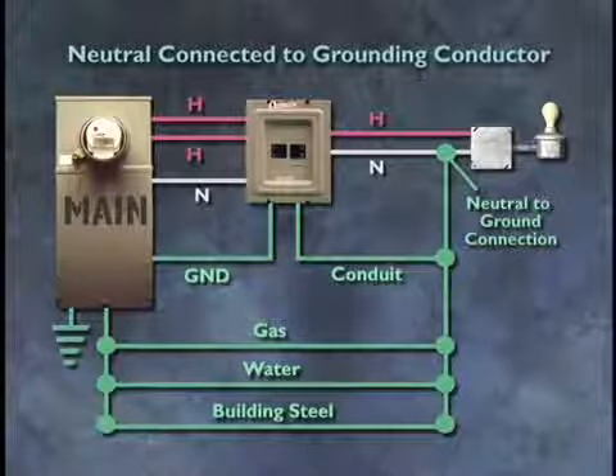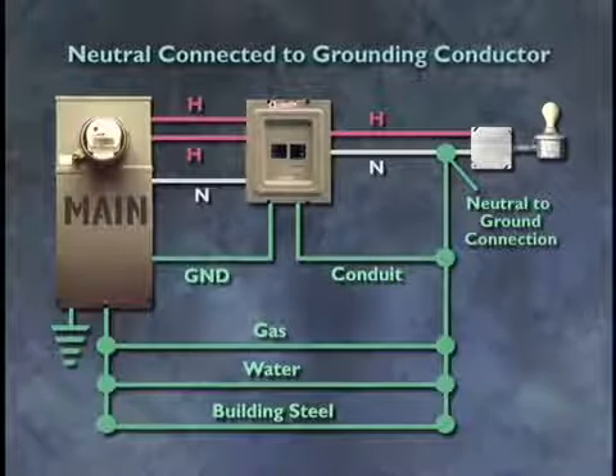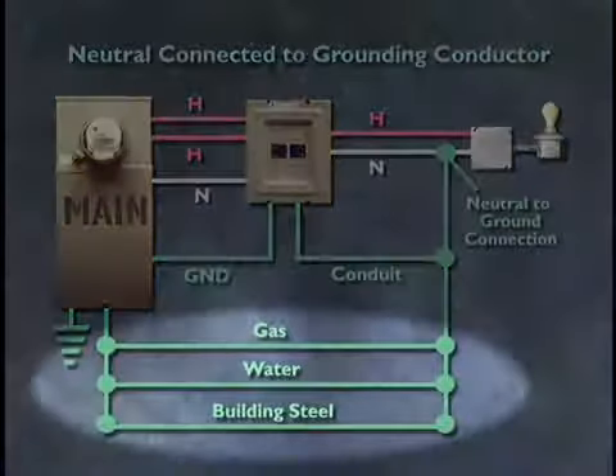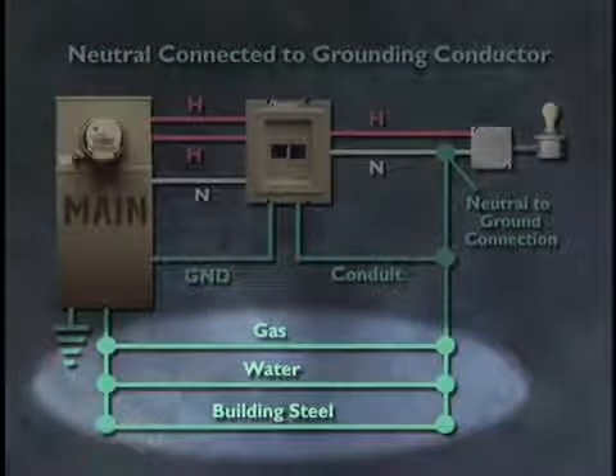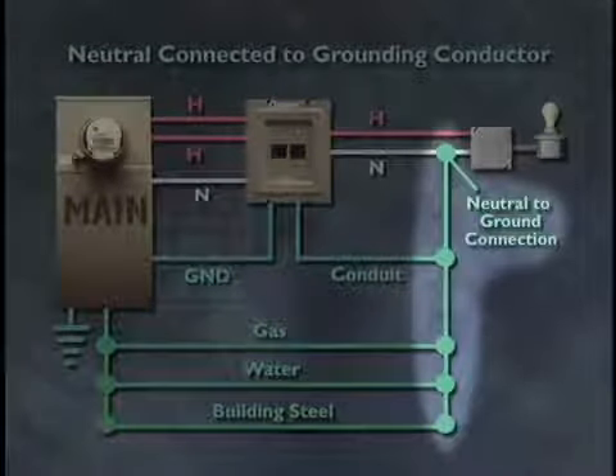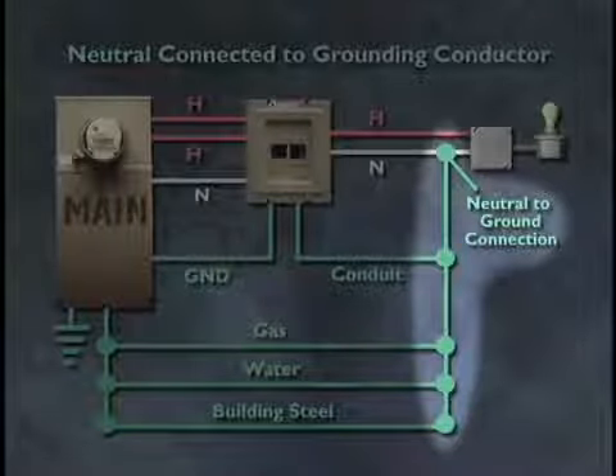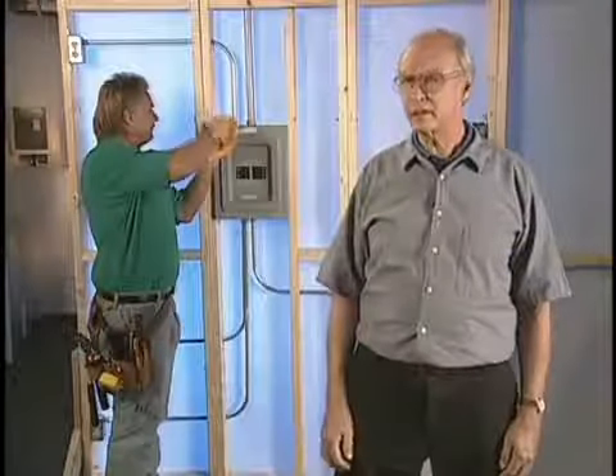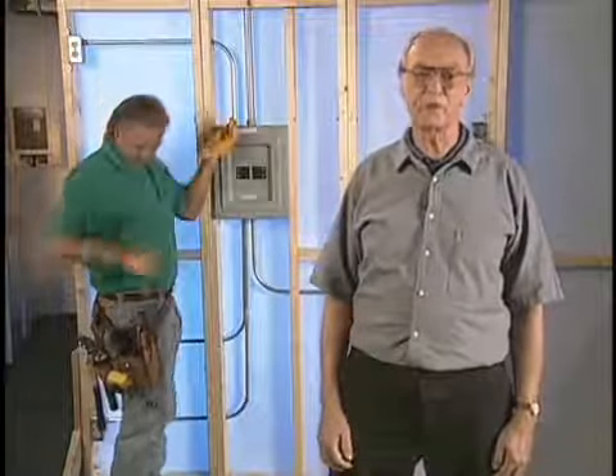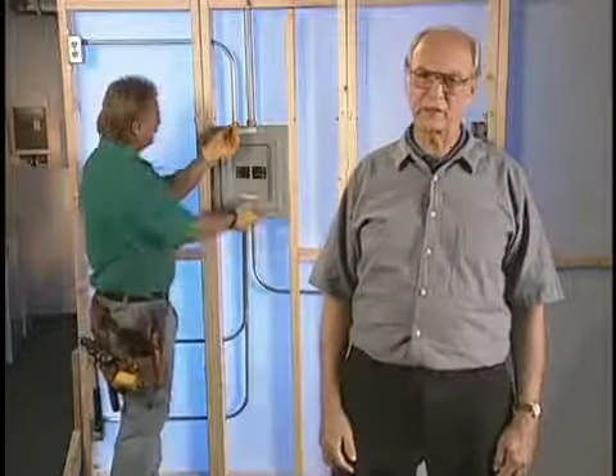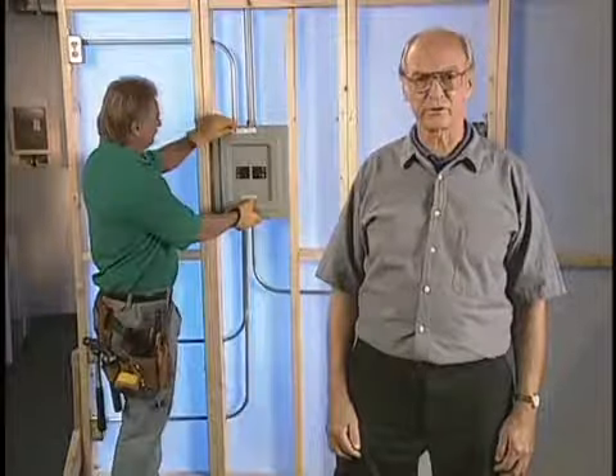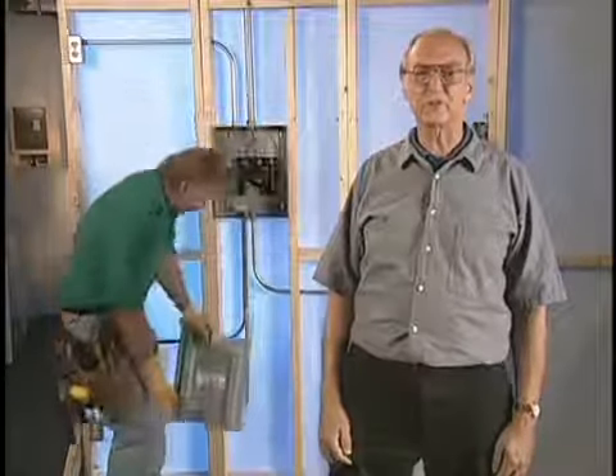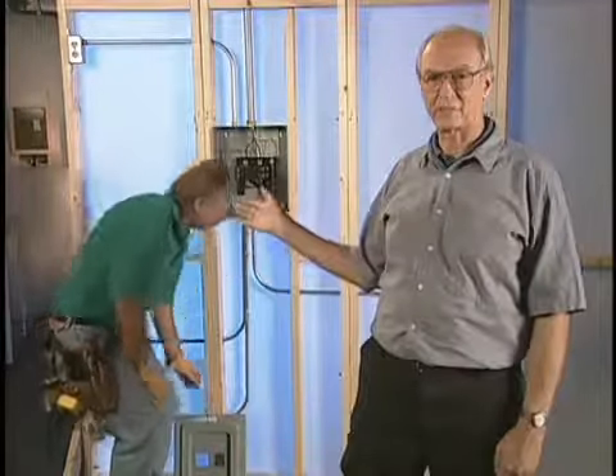This creates a situation in which there are multiple net current sources creating magnetic fields throughout the building. The green paths shown here are carrying neutral current in parallel with the neutral conductor due to a neutral ground connection in the circuit. Now let's look at how these connections come about. There are three fundamental ways neutral gets on grounding conductors. We'll illustrate the main one on our demonstration subpanel.